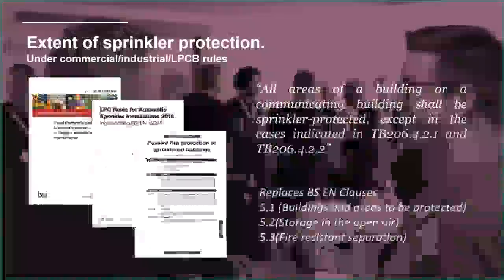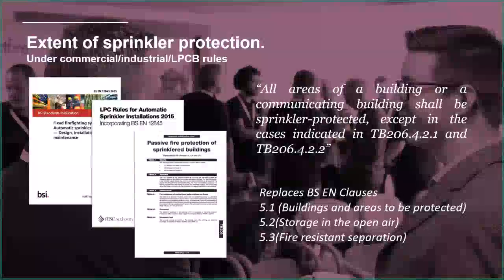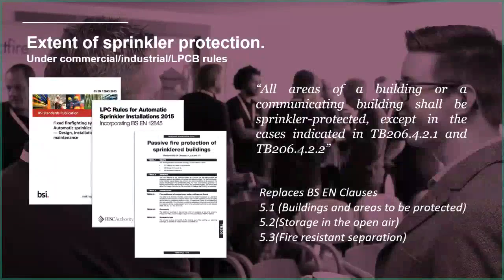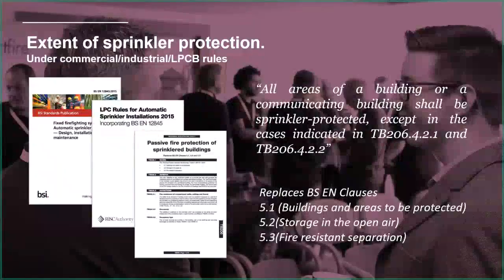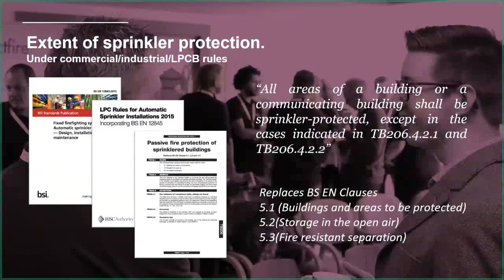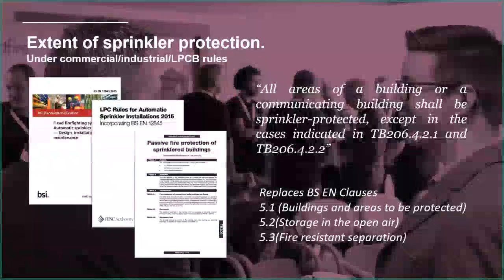Under the industrial and commercial rules, we're looking at the LPCB rules. These are made of several different parts: the British Standard 12845, technical bulletins, and one of these - TB206 - is all to do with passive fire protection of sprinkler buildings and covers areas which do not have to be sprinkler protected. The quote from that technical bulletin is very similar language: all areas of a building or communicating building shall be sprinkler protected, except in the cases indicated below. The technical bulletins give more information and on occasion actually overwrite what the British Standard says.